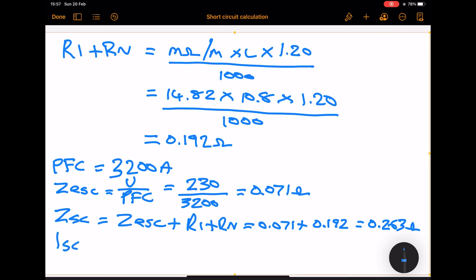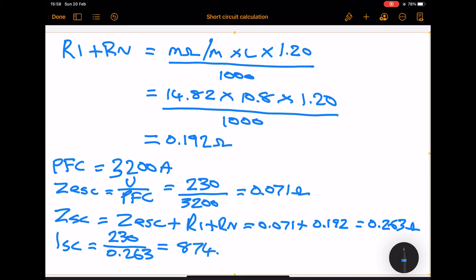To find the short circuit current ISC, we divide the voltage by the ZSC — it's simply Ohm's law, voltage divided by resistance for the circuit. So that becomes 230 divided by 0.263, which gives us an answer of 874.52 amps.